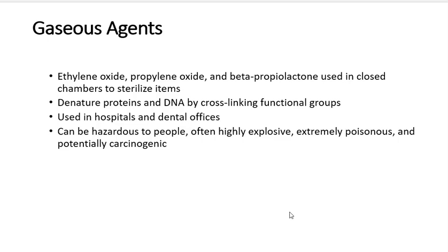I know in the hospital that I worked at, we used the ethylene oxide to sterilize the instruments because we had a very busy OR. And if you have a leak, you have about 8 seconds to get out of the room, and you're told if you walk in there, you hear this alarm go off, get out. Because once the door will close in so many seconds, and if you're not out, you're going to get locked in.